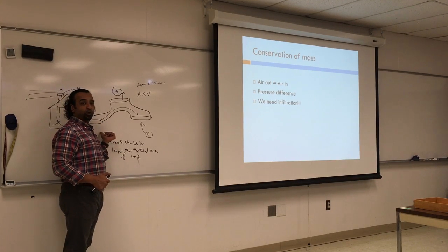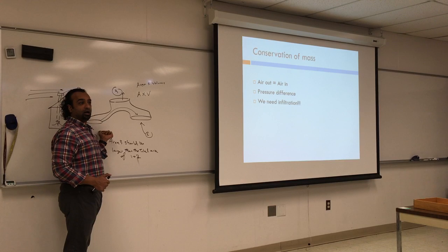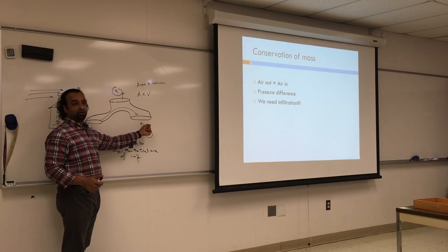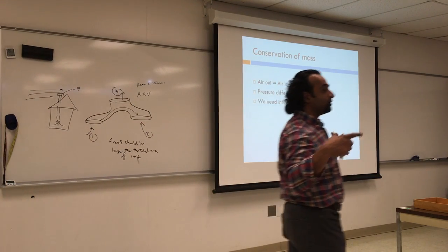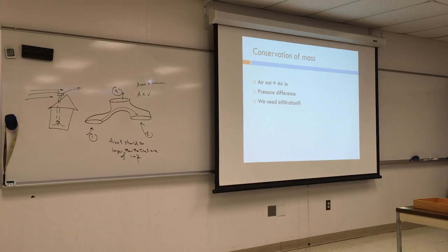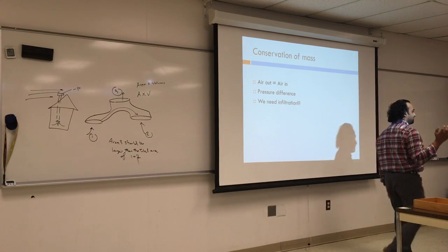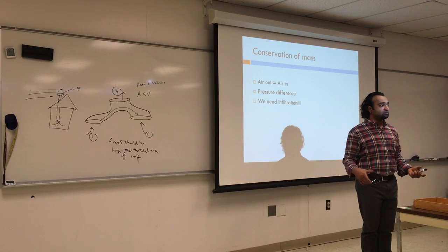2. How would we have that if you have a boiler for house heating, and you have hot water here? If you want to connect 2, make sure that the area coming out is the total of those. Because again, pressure goes to the path of least resistance. It's like electricity. So think about that when you try to install. And I don't want to say too much in this, because we're going to do some math in the other class when it comes to piping. Same thing with water. If you have 2 pipes, again, the trunk is smaller than both pipes, you're going to have backflow, and that's really an issue.